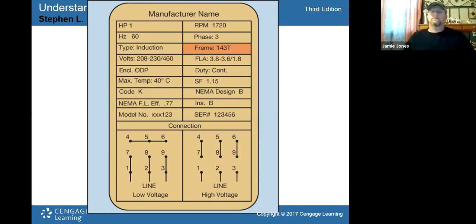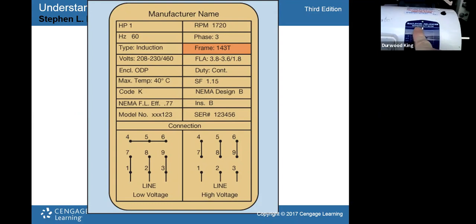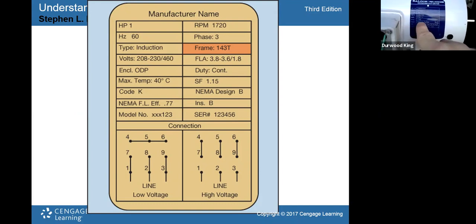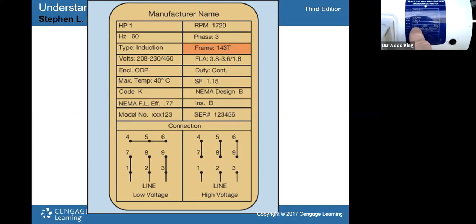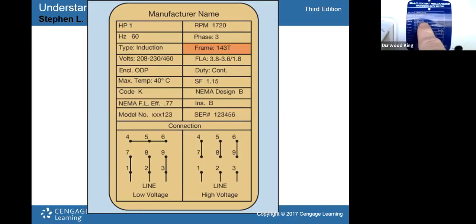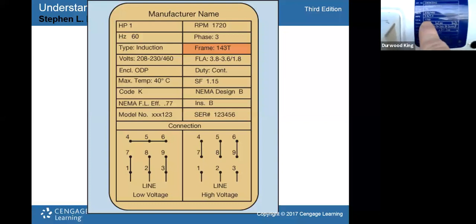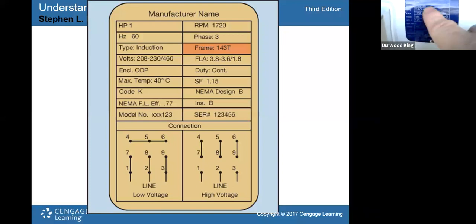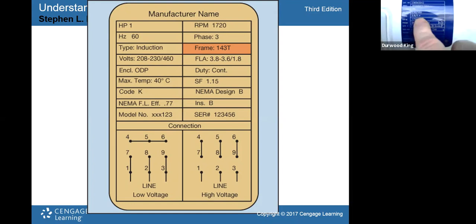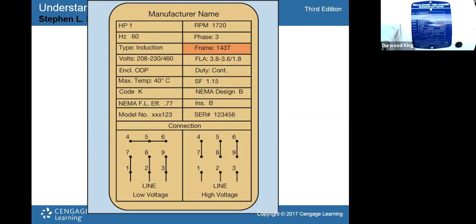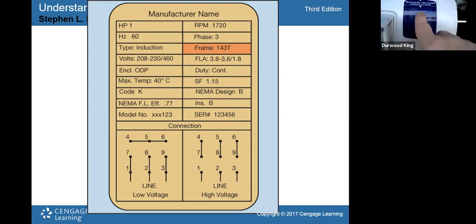So again, if you had to replace it, but your supplier didn't have a Baldor, he says, I've got a Leeson, do you want the Leeson? And you say, well, if it's got a 56C frame, and if it has 230/460 voltage, if it's a 3/4 horse motor, and if it's 1750 RPM, basically those five pieces of information right there, if you match that with any other brand motor, then you're fine. It'll run, because these are standardized things by NEMA.